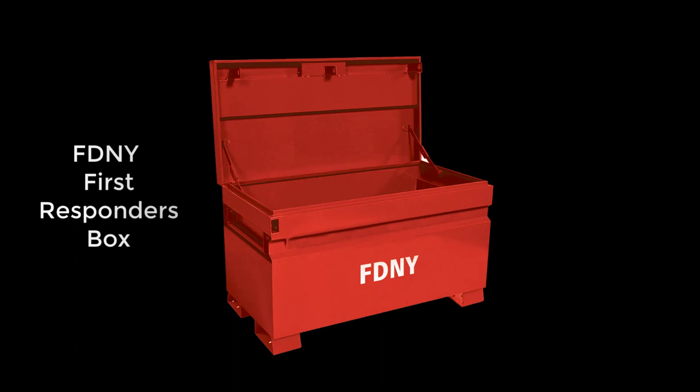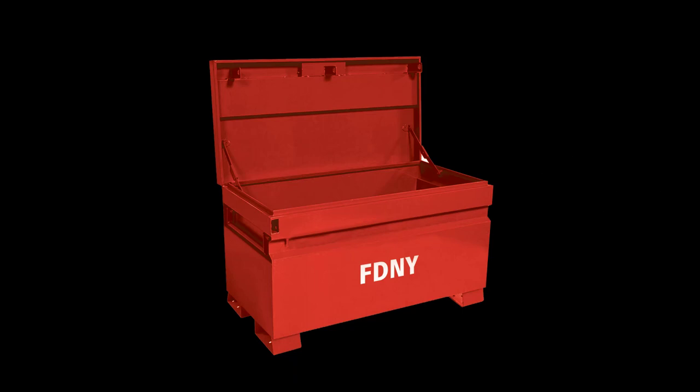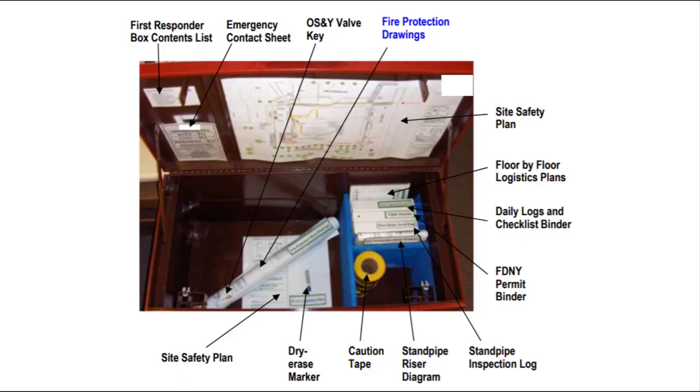All job sites should have an FDNY first responders box. This should be on a solid surface with clean surroundings, easily accessible 24/7. It should have the emergency contact list, contact numbers for site supervisors, site safety managers, superintendents, security contractors, fire suppression contractors, elevator contractors, and electrical contractors. This should also have FDNY permit binders with detailed information with floor plans, standpipe diagrams, and the fire protection system.